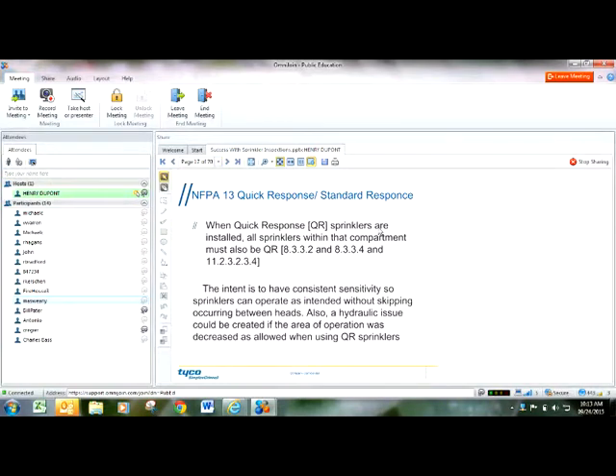Okay, this is something that it's really easy for everybody to identify. Quick response sprinkler heads cannot be mixed with standard response sprinkler heads. Quick response sprinkler heads are tested by the manufacturer to go off at a certain time, so before the fire grows to a point where it can't be controlled by sprinklers. If you have standard response and quick response sprinkler heads mixed together within the same compartment, they're going off sporadically. They're not going off at the time that they were designed to go off at.